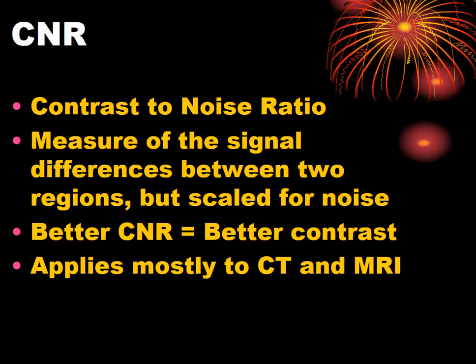CNR — contrast to noise ratio — measures the difference between adjacent areas of the x-ray, such as light and dark regions, while controlling for noise. If you have noise on your x-ray, that compromises your contrast. Better CNR equals better contrast. This applies mostly to CT and MRI, but also to flat radiography. Noise sources for CNR include scatter and quantum mottle.